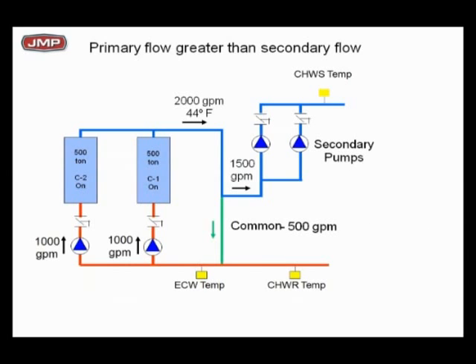Now you see how much fun this can be. So now we've got, going south, 500 GPM in the common pipe of 44 degree water. Great. So you see how the T's have to sum up? I take my 1,500 GPM of 44 degree water out to my system, and I bring back 1,500 GPM at 56 degrees, and it's going to do what at the T? I'm going to have 1,500 GPM of chill water returned at 56 degrees, mixing with 500 GPM of 44 degree water to give me 2,000 GPM of 53 degree water returning.